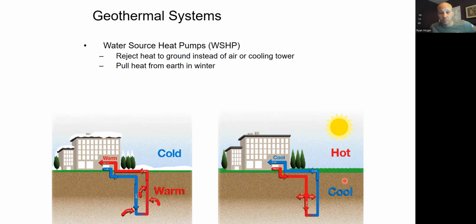And as I'm doing that all summer long, guess what happens to the ground temperature? The ground starts heating up. By the way, in most areas, when you get below the frost line, the ground temperature doesn't change throughout the year, unless you have like an aquifer flowing water through it or something weird like that. But other than that, once you get below the frost line, the ground temperature is almost the same year round. But if I've got a geothermal heat pump dumping heat into the ground all summer, the ground gets warmer and warmer and warmer, which is great. I'm cooling off my water, and I'm doing it without running a cooling tower.